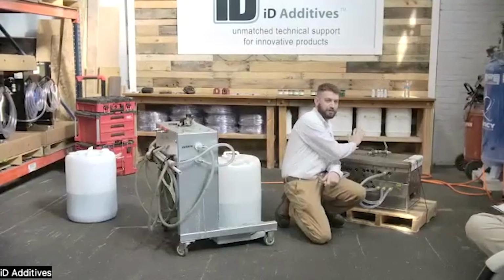And I'm kind of getting ahead of myself a little bit, but when you're ready to shut this down, I lift up on the supply lance until my supply line runs clear. That way I know that the water on the internal lines of the pump are shut off. Move my air over to the blowout side. Again, back to that, turning that three-way valve. And I blow all the water back into the water drum. And this step can be achieved, like I mentioned before, if you have a dedicated leak testing station or a water pressure station, you can do this step at that time.